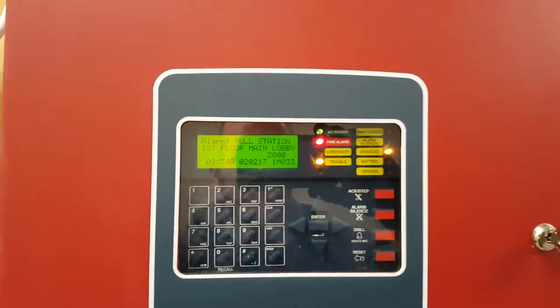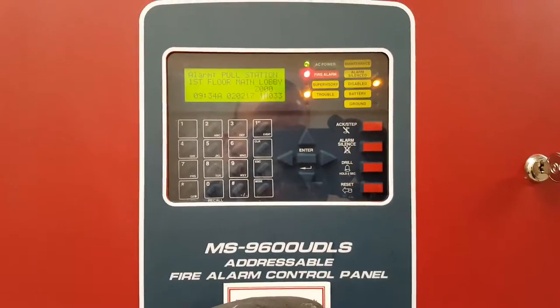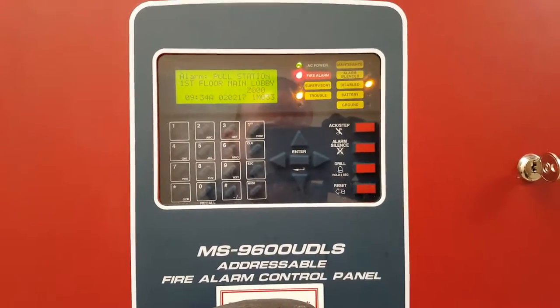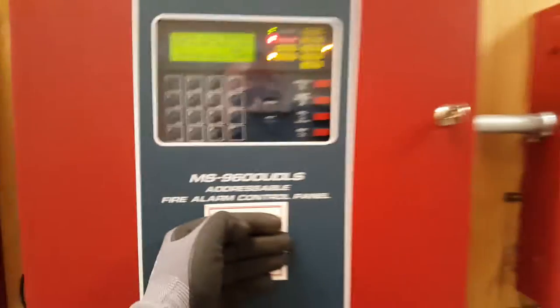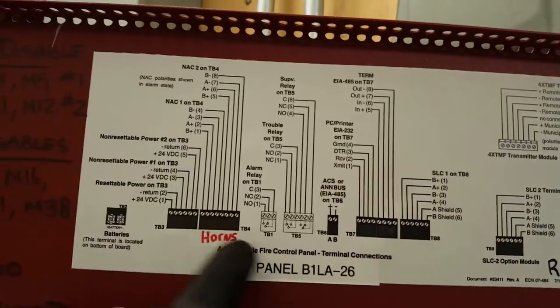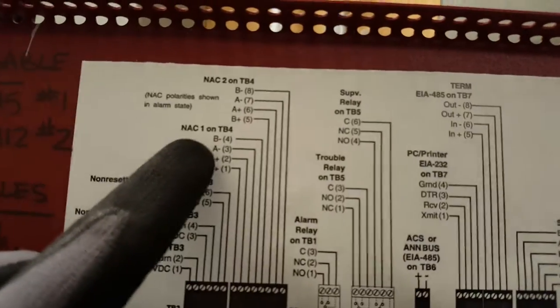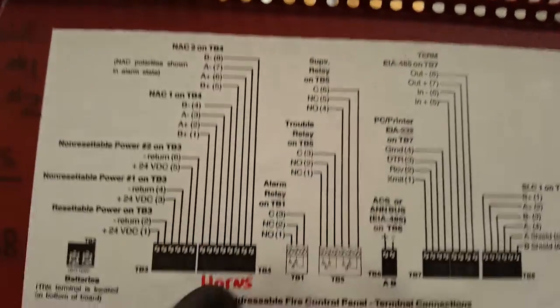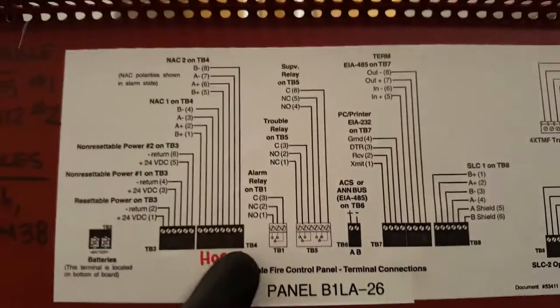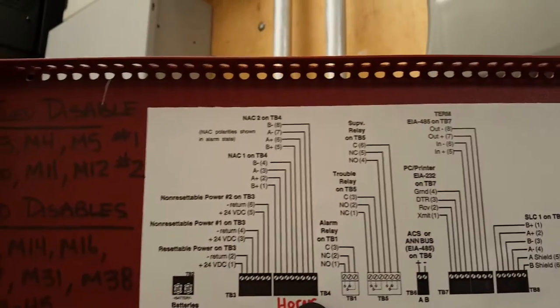This video is going to show you how to disable the NACs on a MS9600 UDLS Fire-Lite panel. What you're going to want to do first is go to your legend or your map and you're going to see the connections. You're going to see the NAC circuits here — NAC1, NAC2 — on the TB4 connection.